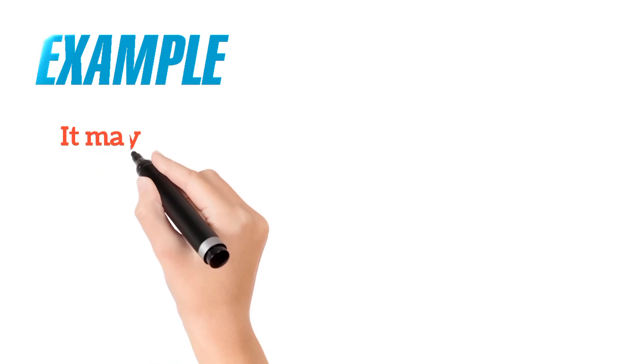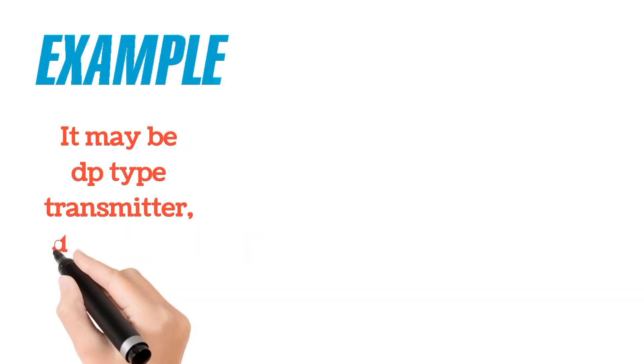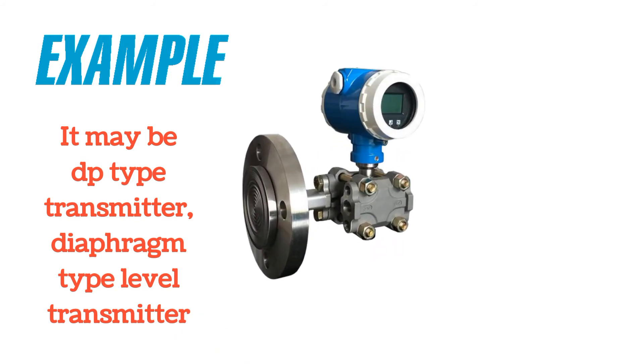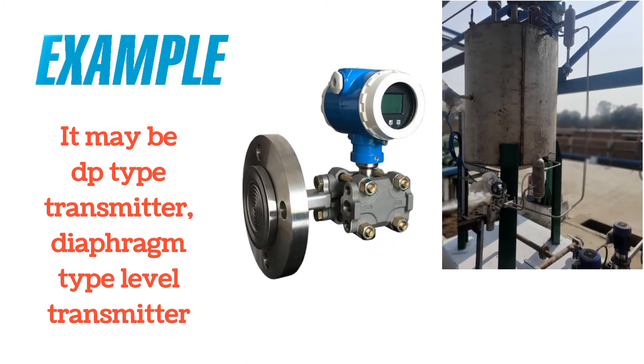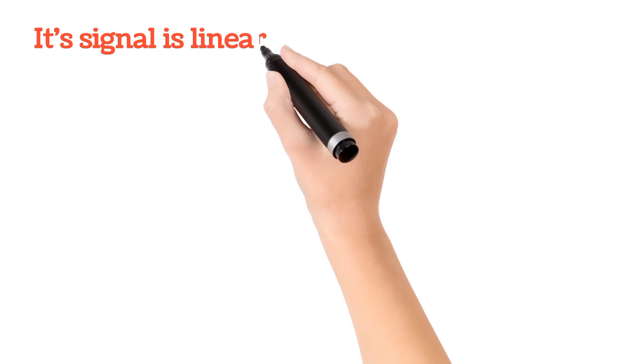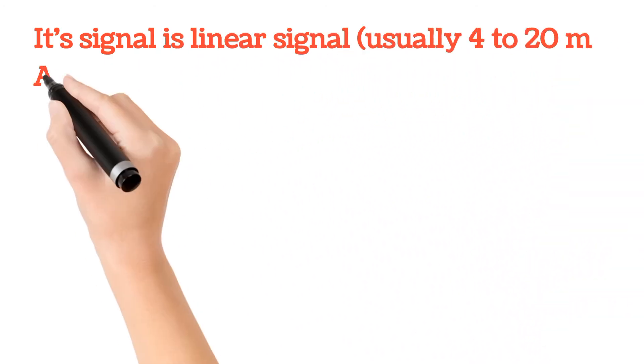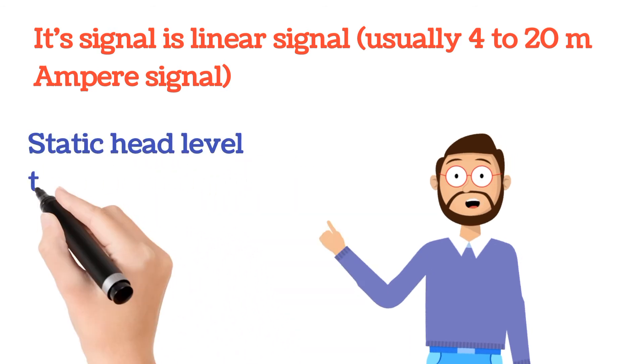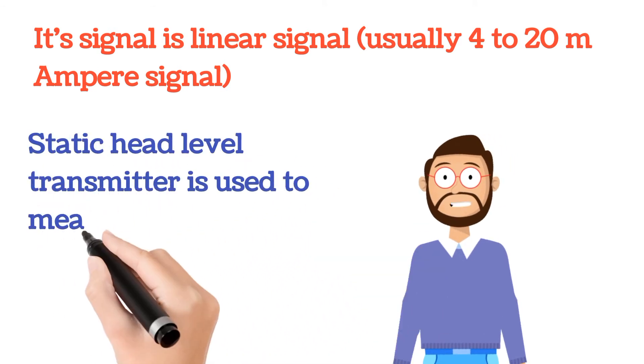Examples of static head level transmitters include the DP type transmitter and the diaphragm type level transmitter. The DP type is shown on the right side image and the diaphragm type on the left side image. Its signal is a linear signal — usually 4 to 20 milliampere — and it measures the total liquid level.